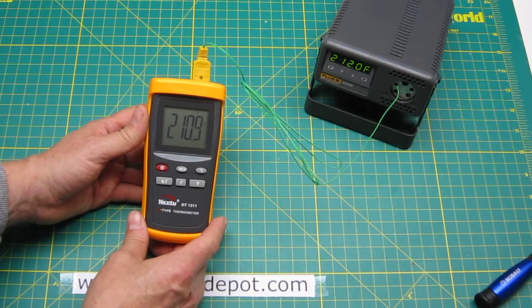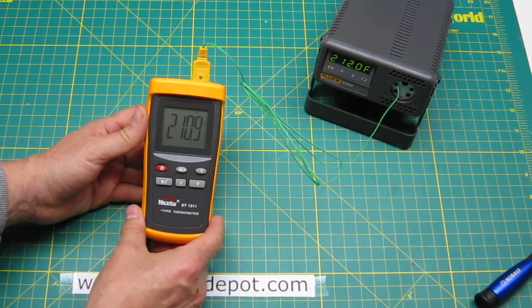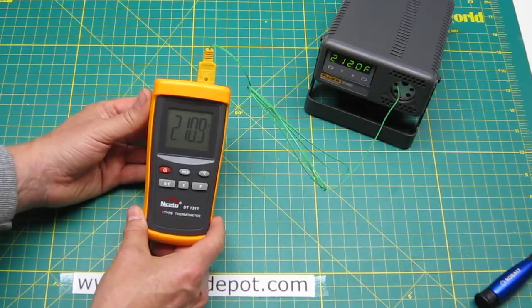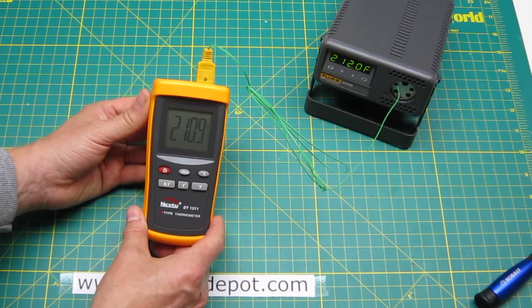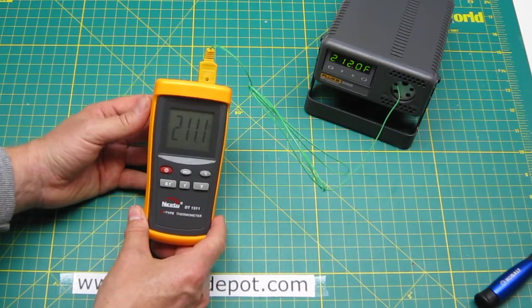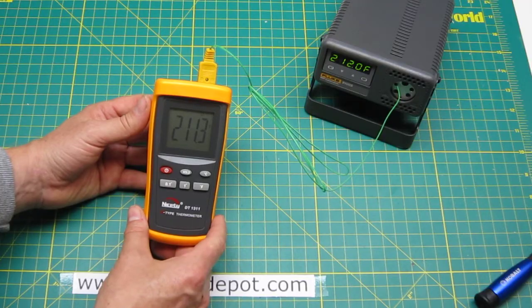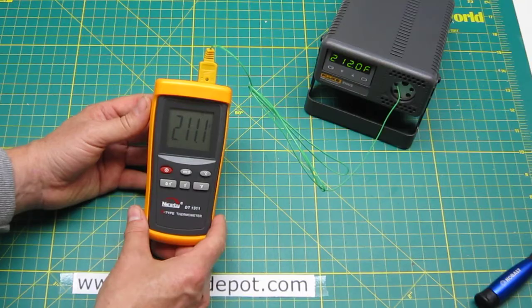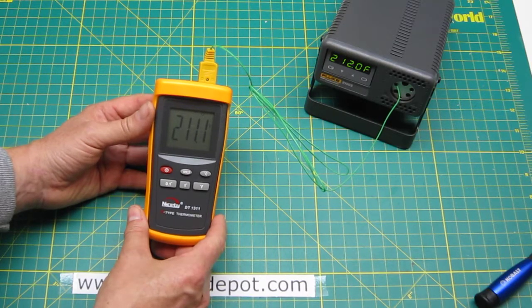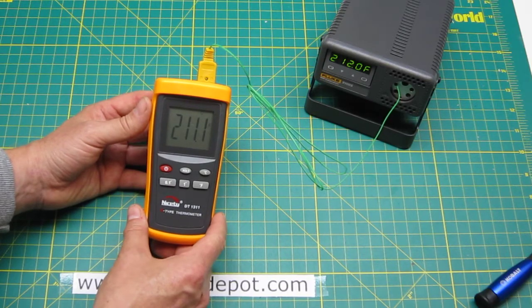It seems to have stabilized and the temperature should be 212 degrees Fahrenheit. It is at 211.3 here right now. So it's within one degree of the actual temperature and I think this is pretty good.